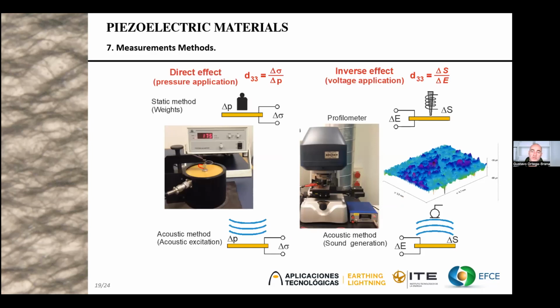Okay, the piezoelectric coefficient can be measured in two ways, by quasi-static and dynamic measurement. This is because the response of piezoelectric material changes with frequency. Each of the two methods can be made by the direct effect, by applying a force, or the indirect effect, by applying an electric field. For the direct effect, commercial devices can be found in the figure on the left, where the sample is pressed at constant velocity and the charge is measured directly on the display. This device works at low frequency.